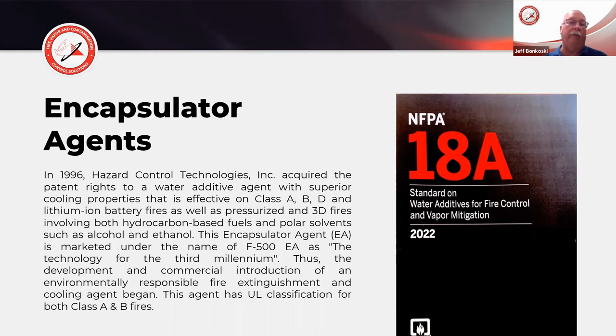When we look at the NFPA 18A standard in section 7.7, it addresses the spherical micelle stability test. The test: take a gallon of a flammable liquid, 16 ounces of the concentrate, and 5 gallons of water. After that's turned into a solution, it's allowed to sit for 1 minute. At the end of 1 minute, a torch is passed across the entire surface of the pan, and there can be no visible flames.